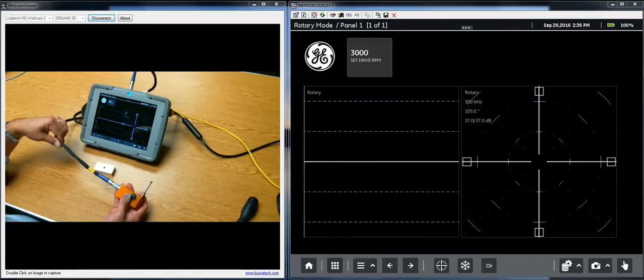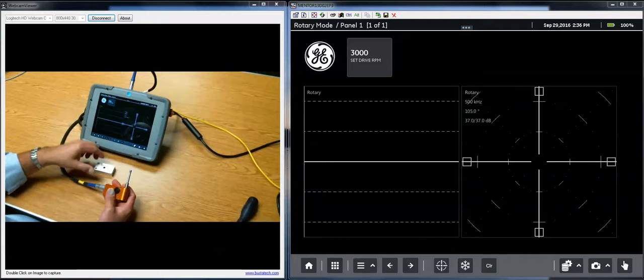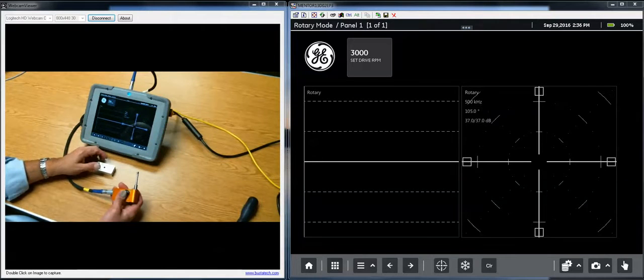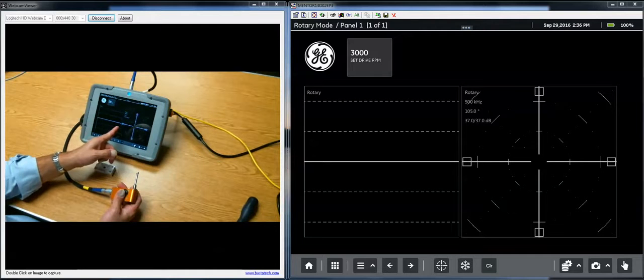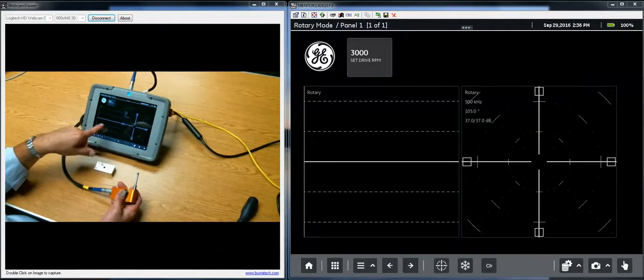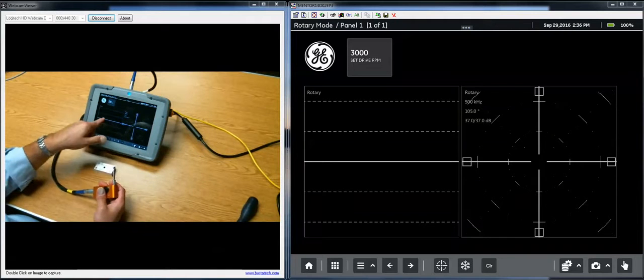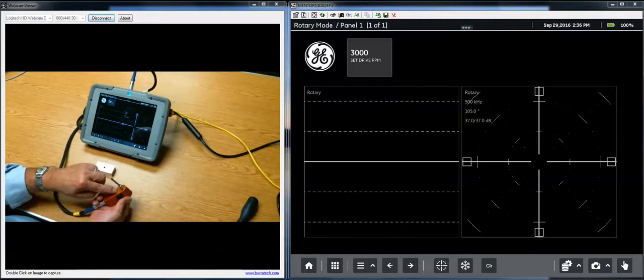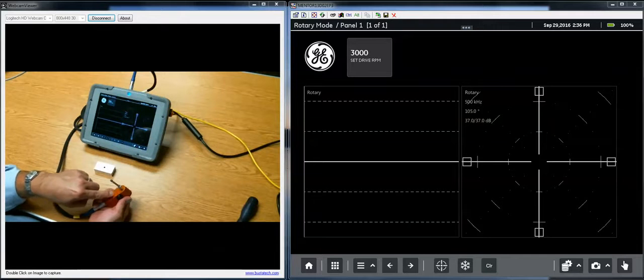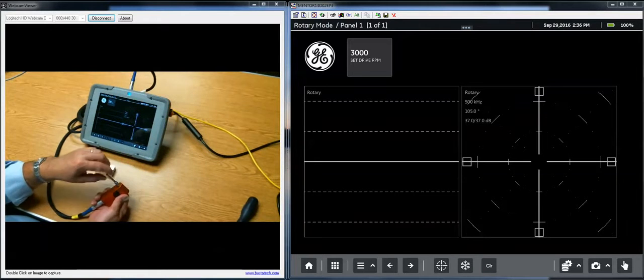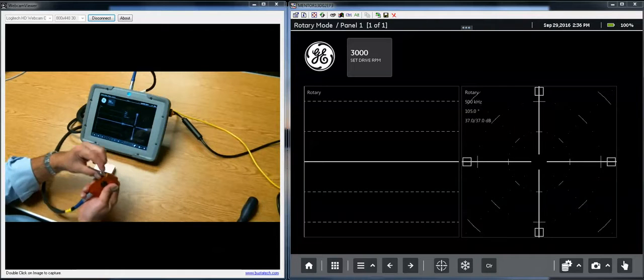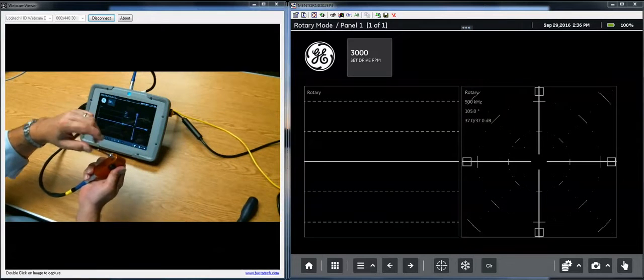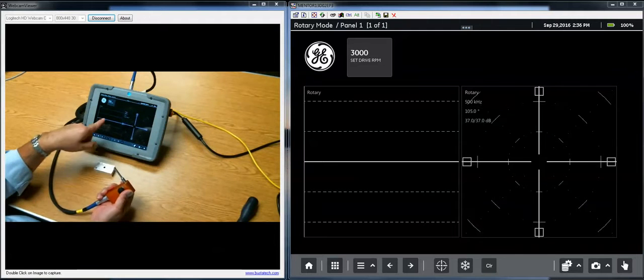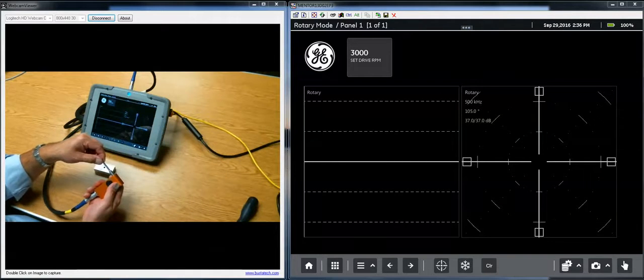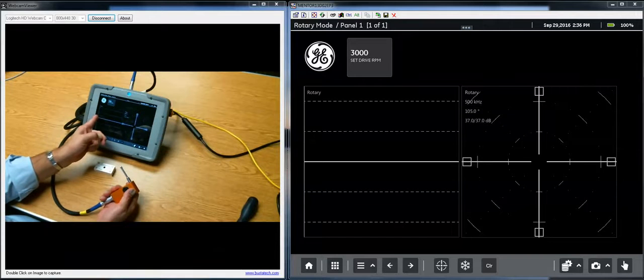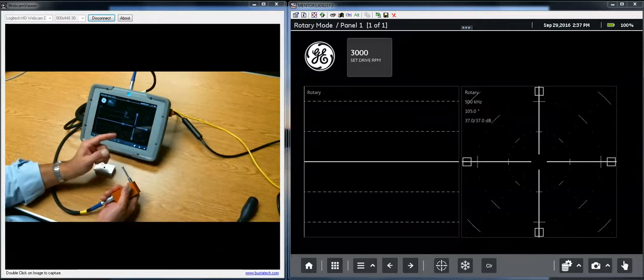The instrument will automatically detect that you have a rotary drive plugged in. It will change the behavior of the strip chart, or the time-based view, to show you exactly one rotation at a time, or some number of rotations that you get to choose at a time on the strip chart. So there's an index detection inside the probe, inside the drive, and it will detect when the red dot here on the probe is aligned with the cable, and it will put that at the center of the screen. And as the probe makes exactly one rotation, it will go from the left side of the display to the right side of the display on the time base.